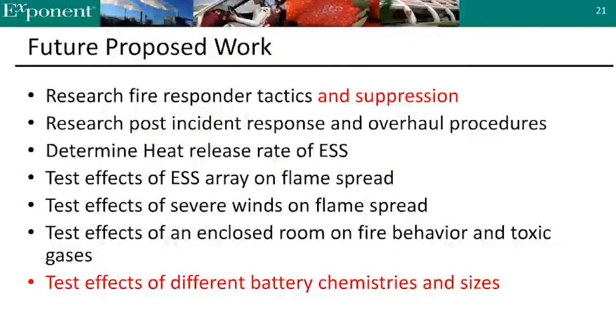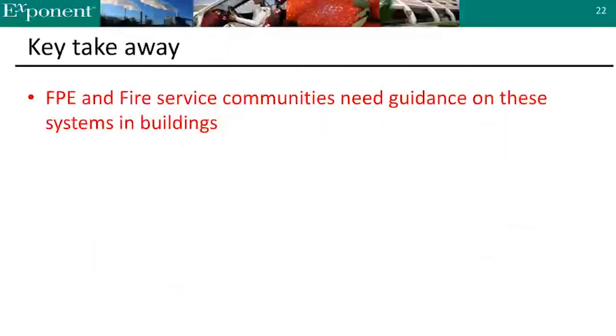As a result, we ended up with about 7 key takeaways in areas for future proposed work. The work we're here to talk about today is highlighted in red: how do you suppress these fires, and what are the effects of different battery chemistries and sizes on the hazard that can be faced on these different energy storage systems. But there was one common theme: the fire protection engineering community as a whole, as well as the fire service communities, really needed guidance on these energy storage systems inside of buildings where they could have an effect on the building, on occupants, and general life safety.